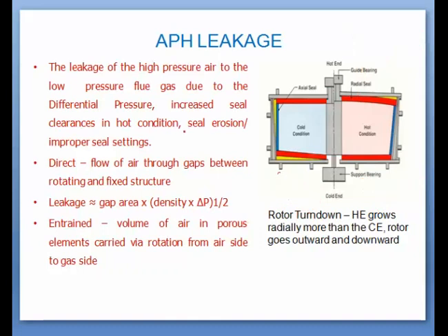There are some other reasons, that is the increased seal clearance in hot condition. Generally seal clearances increase during the hot condition because of seal erosion with the span of time and improper seal setting. So these are the reasons due to which the leakage or short circuiting between the cold air and hot flue gases may occur.